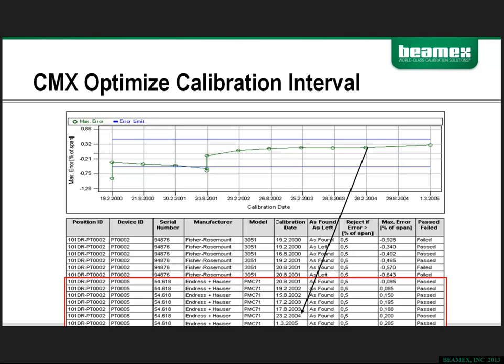And the next black line now is pointing out the fact that in February 2004, they adjusted the calibration interval, which is represented by, you see a circle here, and the next circle doesn't appear for almost a year. So what we've identified is that, okay, we've changed that interval to a year, but yet the drift is still minimal, and we've expanded that out to a 12-month period now with very minimal decrease in performance for that particular asset.